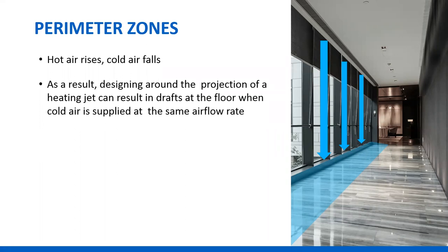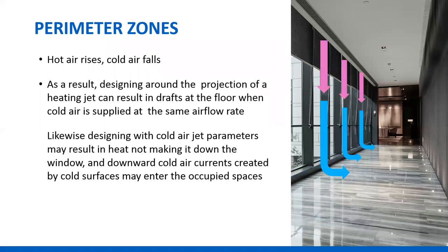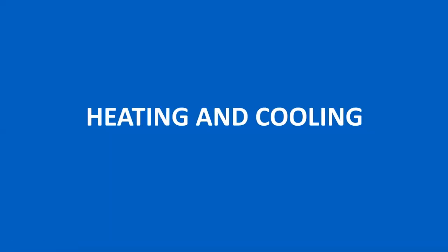When you put cold air at the same flow rate, it's going to go a lot further. If you're dealing with a cold air jet and you try to keep it from entering the occupied zone at the floor, if you use the same airflow for heat, it may not make it down far enough to provide comfort. So we have to look at both heating and cooling performance of the diffuser and decide what to do.